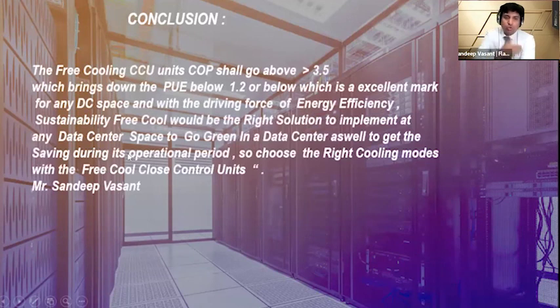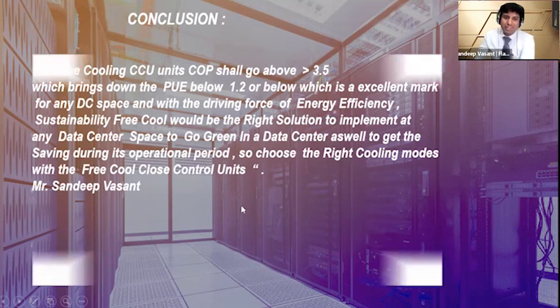So as a conclusion, we spoke on what goes into the ISHRAE norms, what is the methodology, what is the solution, and free cooling. As a conclusion summary, I would like to quote that the free cooling close control unit COP shall go above 3.5, which brings down the overall PUE to 1.2 or below, which is an excellent mark for any DC space. And with the driving force of energy efficiency and sustainability, free cooling would be the right solution to implement at any data center, to go green in a data center, as well as to get the savings during the operational period. So choose the right cooling modes with the free cooling close control unit.